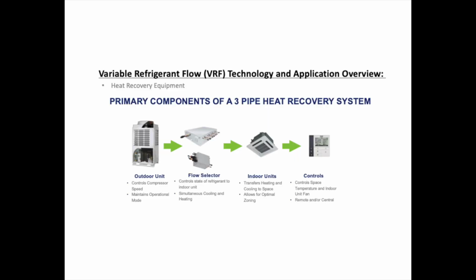Let's look at a three-pipe system. Let's look at the primary components of a three-pipe heat recovery system. Same thing, you've got your outdoor units, you've got your indoor fan coils, and you've got your remote controllers. In a three-pipe system, we call them the flow selector boxes, and this is what controls the state of the refrigerant going from the outdoor unit to the indoor unit. And this is also what allows for simultaneous heating and cooling.